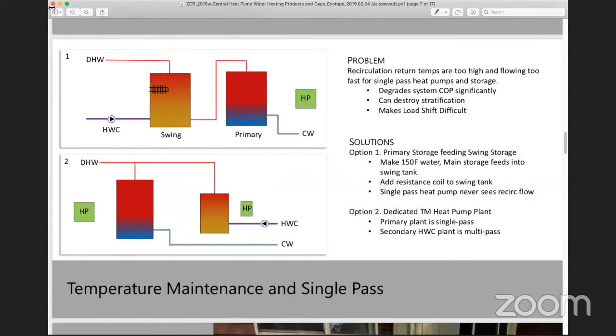So when we're talking about demand response, having a strategy for recirculation is really important. We've got two strategies internally, and I'll review those. The first strategy is up in the upper left. You've got a primary tank that's heated by a heat pump, and then you have what we call a swing tank. That swing tank is not connected to the primary heat pump, and it's just sitting downstream of your primary flow, and you flood it every time there's demand in the building. You fill that tank up, and then your recirc slowly bleeds it off. We typically put a backup resistance coil in here, but if you size it correctly and keep the primary at about 150 degrees, we've found we don't trigger that resistance element. We've got a couple of pilots going now testing this theory. That's more of our recent development.